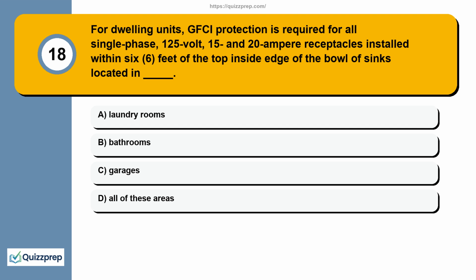Question 18. For dwelling units, GFCI protection is required for all single-phase, 125-volt, 15 and 20 ampere receptacles installed within 6 feet of the top inside edge of the bowl of sinks located in laundry rooms, bathrooms, garages, all of these areas.